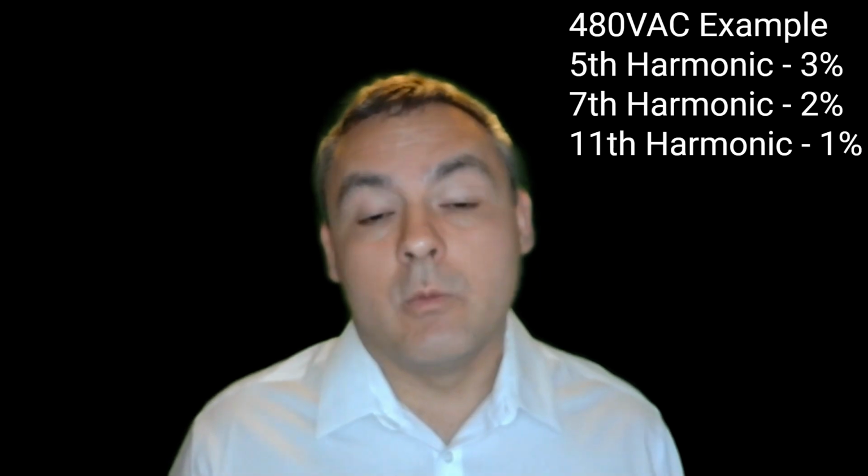Remember, the voltage example from video one that had the waveform of 480 volts AC with 3% on the fifth harmonic, 2% on the seventh harmonic, and 1% on the 11th harmonic.